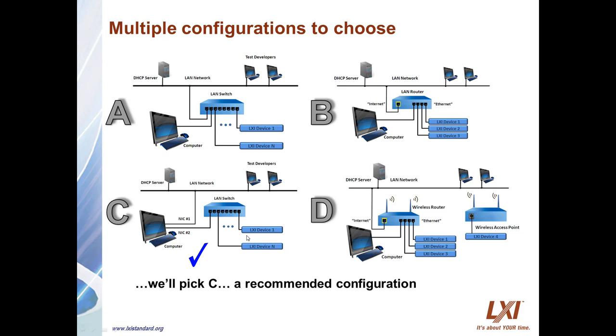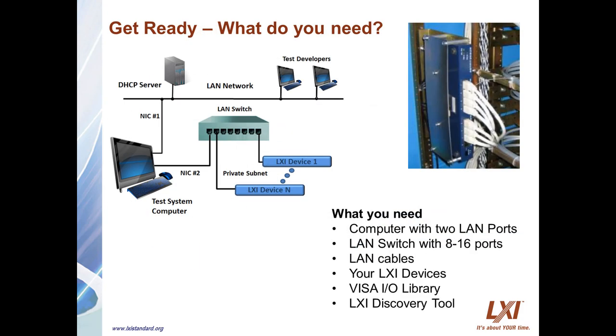Configuration C is really what we want to focus on — it's the recommended configuration for an LXI-based test system. To get a system like this started, you need a computer with two LAN ports or two LAN network interface cards, a switch with plenty of access for multiple devices, lots of LAN cables, and of course your LXI devices. You typically need the VISA I/O library to program these devices from your computer, and to discover what devices are on your network, you'd use the LXI discovery tool.